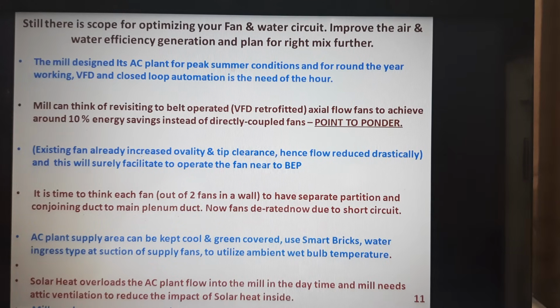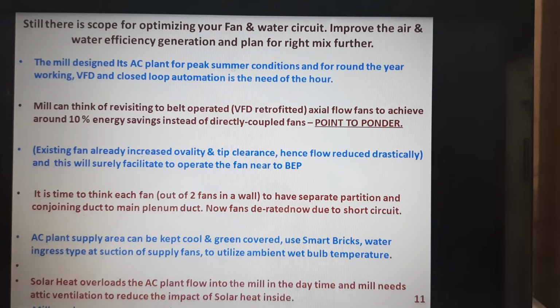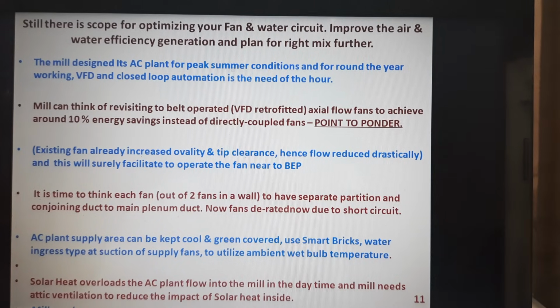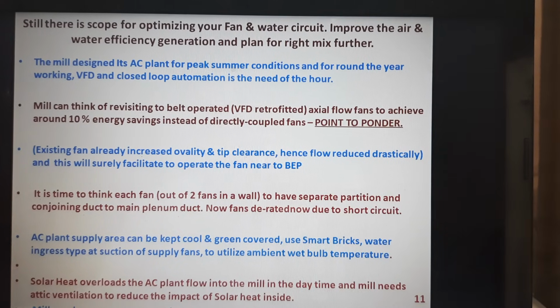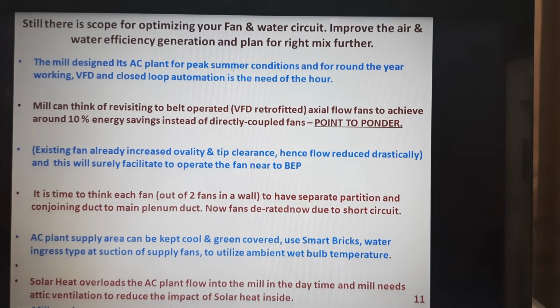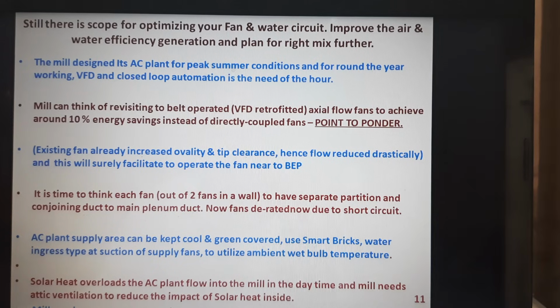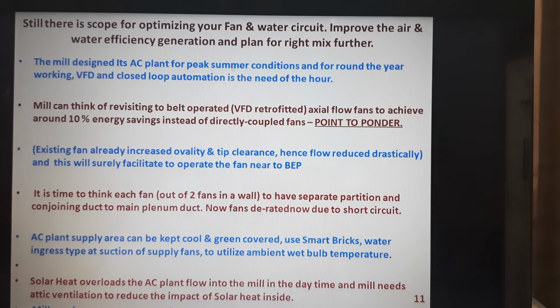Now, I am trying to say, let us try to rethink axial flow fans. It is operated directly. The motor is coupled directly to the fan, and previously, decades back, it was only belt operated axial flow fan with a cogged belt and resized pulleys. Definitely it can give an energy savings of 10%, by adjusting the torque delivered by the motor, optimized to match the demand of the axial flow fan. This the mill can take up, it's a point to ponder. Definitely the mill can take up this way as such.